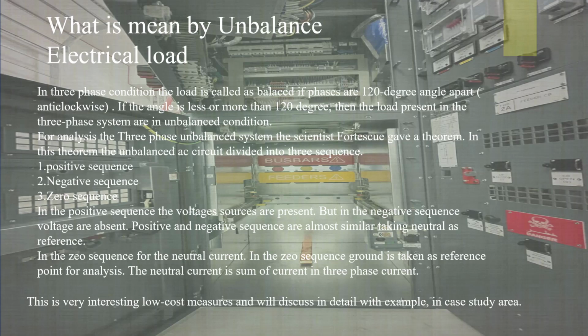In the positive sequence, the voltage sources are present, but in the negative sequence voltage sources are absent. Positive and negative sequence are almost similar, taking neutral as reference. The zero sequence is for the neutral current. In the zero sequence, ground is taken as the reference point for analysis. The neutral current is the sum of the currents in the three phases. This is a very interesting low-cost measure and we'll discuss it in detail with an example and case study.